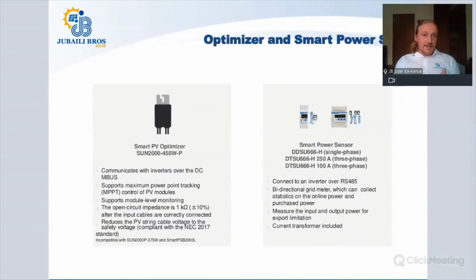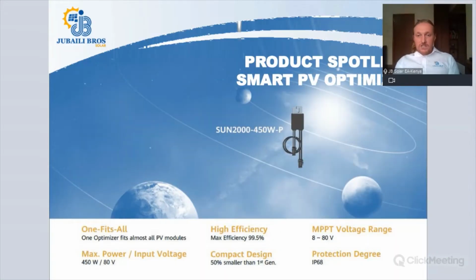Now on the left side, let's look at the PV optimizer. This is a device that acts like a module-level MPPT. I won't go into too much detail today since the focus is on the Luna, but I wanted to bring it up because of a special feature I'll mention later. This is what the optimizer looks like, and its max power is 450 watts, so your panel must be 450 watts or below.